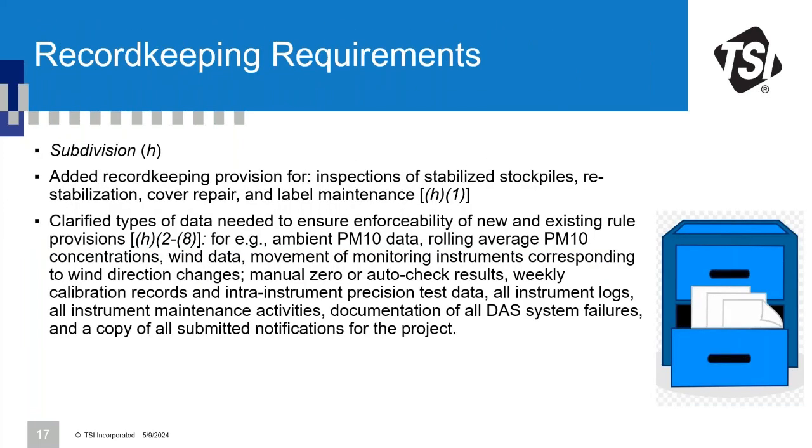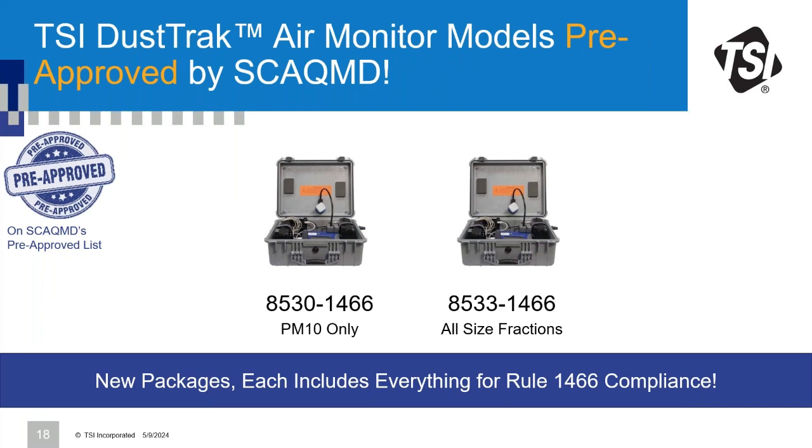One thing as well, as I mentioned, is calibrating to the devices, to your second device. There is an intra-instrument precision test that you would do. When doing that test, you want to make sure you have the data that backs it up. Typically, if you're renting the equipment, that test would be done where you pick up the equipment from. But any test that you do, you'd want to store that record to be able to produce in case it's asked for.